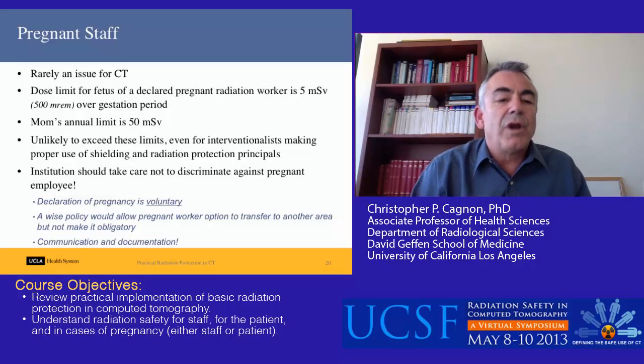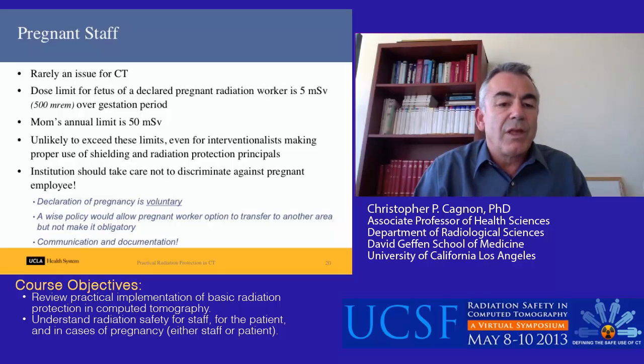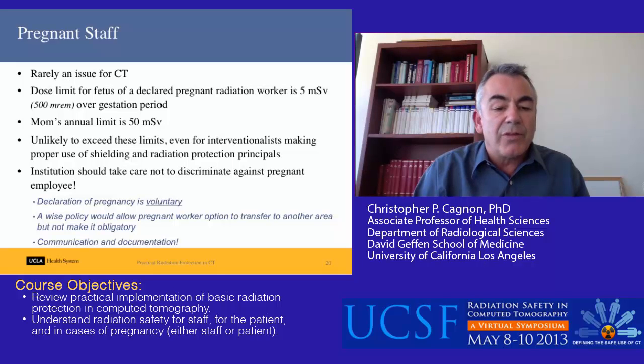Lastly, pregnant staff. This is rarely an issue for CT because the scan room is shielded and you can stand in the control booth with very small exposures. For those who must be in the procedure room: the dose limit for the fetus of a declared pregnant radiation worker is 5 millisievert (500 millirem) over the gestational period — compared to mom's annual limit of 50 millisievert. It's very unlikely anyone would exceed these limits if they make proper use of shielding and the radiation protection principles discussed. Institutions should take care not to discriminate against pregnant employees; declaration of pregnancy is voluntary. A wise policy allows a pregnant worker the option to transfer to another area with less radiation, but not make it obligatory. Communicate and document all discussions about pregnancy and precautions taken.